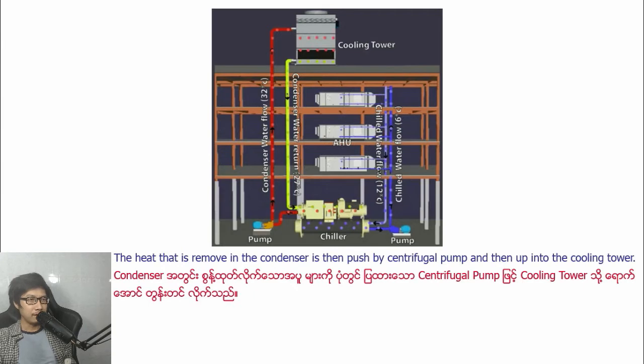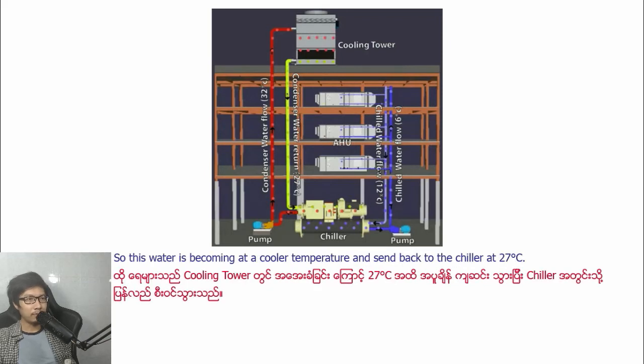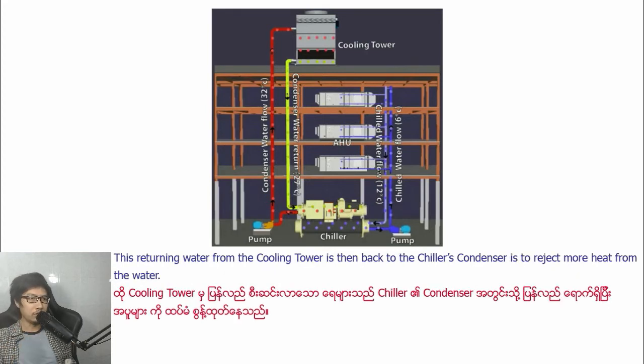The heat that is removed in the condenser is then pushed by a centrifugal pump into the cooling tower. In the cooling tower, air is forced by a fan inside and that dissipates and rejects the heat from the water. So this water becomes a cooler temperature and is supplied to the chiller at 27 degrees Celsius. This return water from the cooling tower then goes back to the chiller to reject more heat.